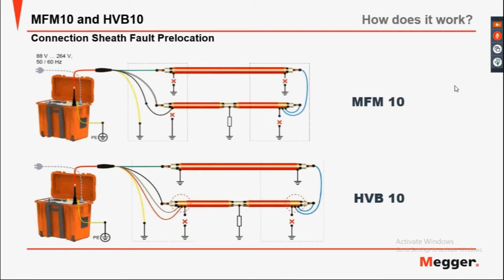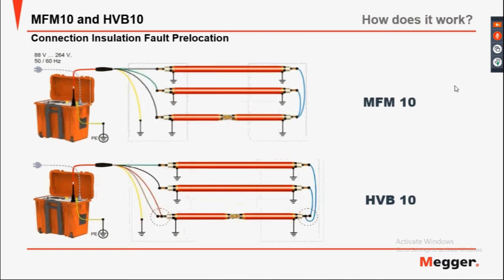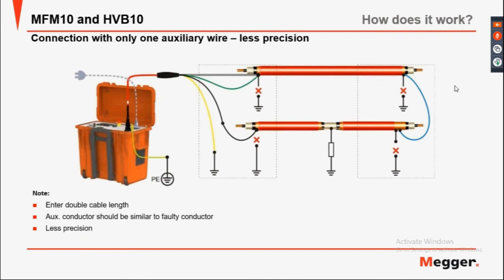Connection for sheath fault pre-location. Connection for insulation fault pre-location — there is a difference between the MFM10 and the HVB in how you connect for a sheath fault pre-location. Connection with only one or zero auxiliary wires: note that you must enter double the cable length. The auxiliary conductor should be similar to the fault conductor, though this is less precise.